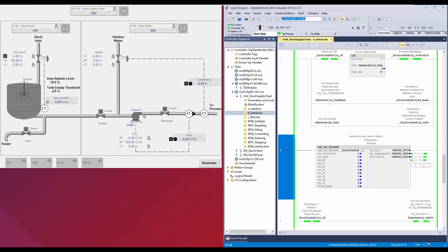When used as permissive, the instruction OUTOK status is monitored only to start a function. Once the function has started, the status is neglected. In an interlock usage, the instruction OUTOK status is monitored all the time while the function is active. If any of the interlock conditions fail, the function is aborted.